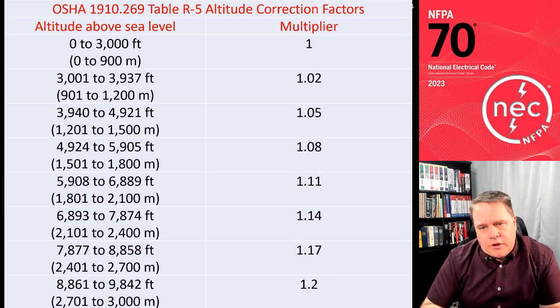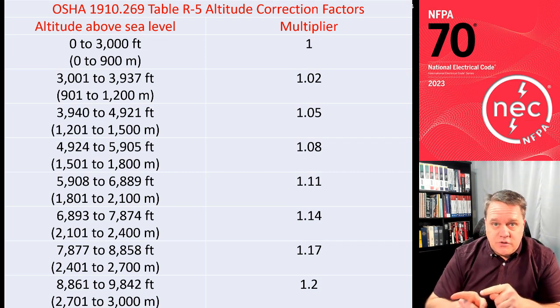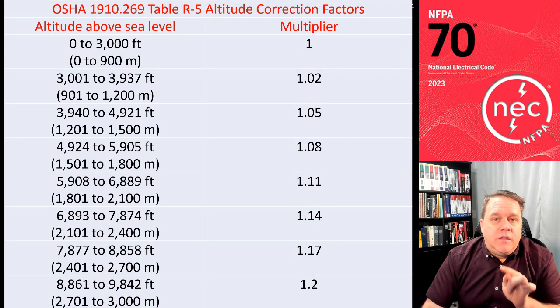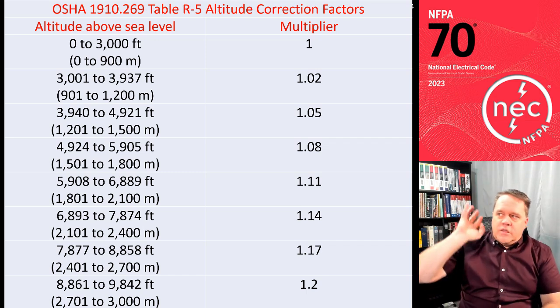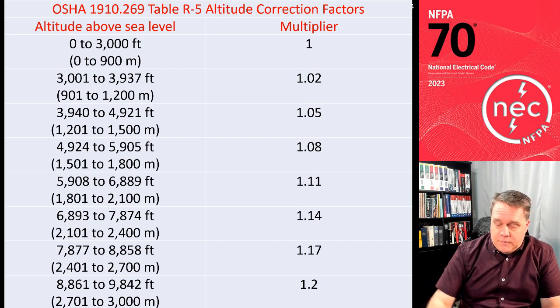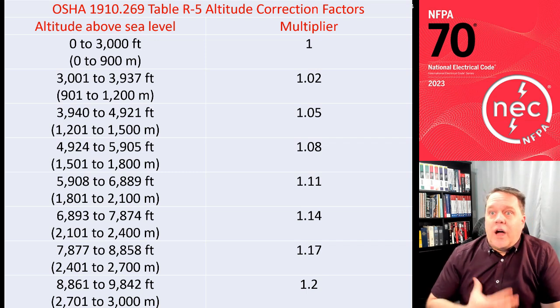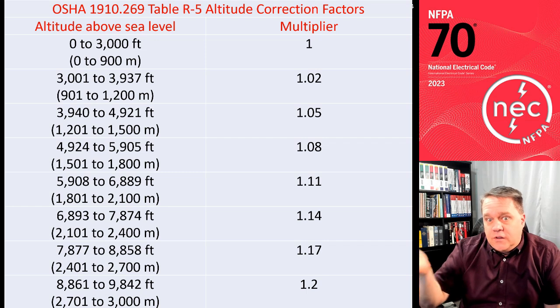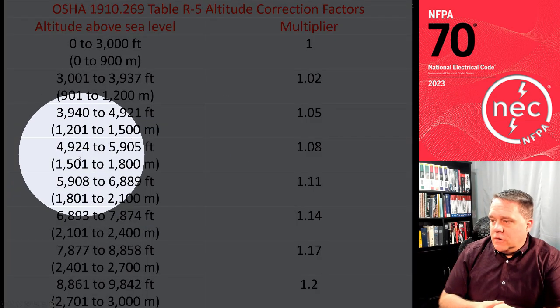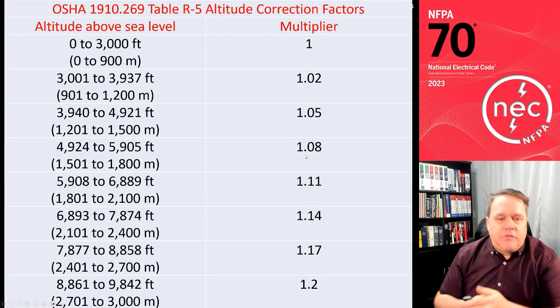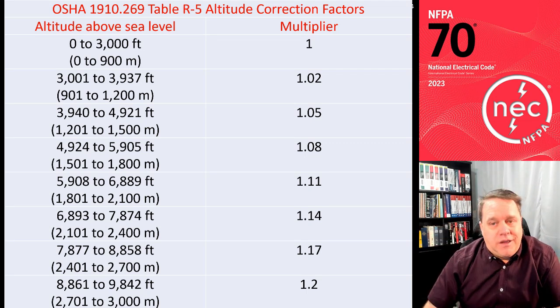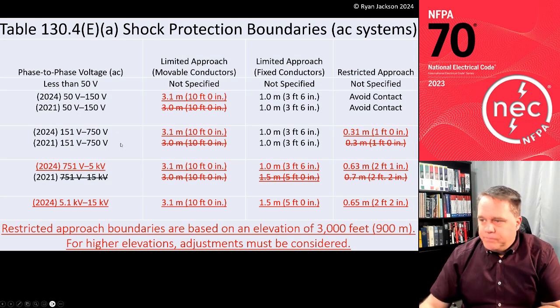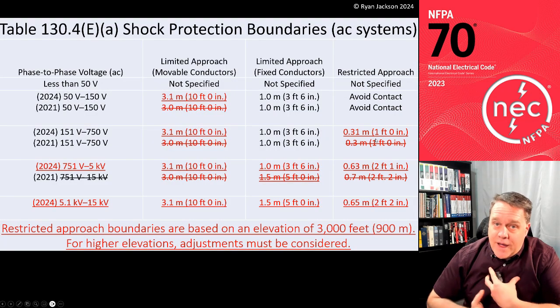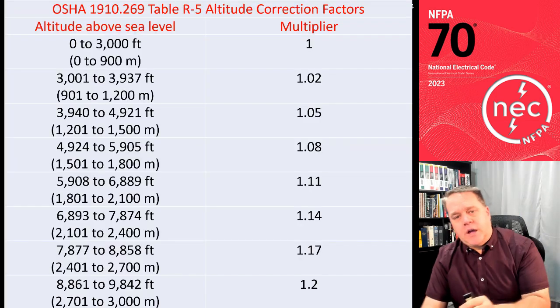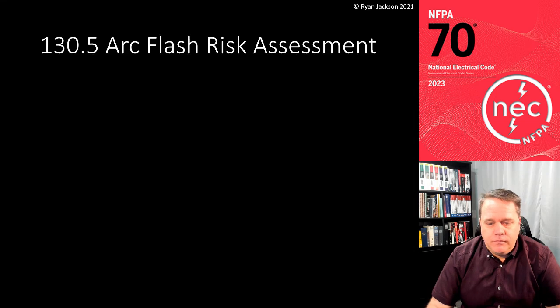So OSHA has this table here, and it says, look, you're going to take the approaches that we just talked about, the restricted approach, and you're going to multiply it by these correction factors based on your altitude. Okay, so this table here is actually not in NFPA 70E because the standard just says, hey, you might need to consider something. Well, I went back and I looked at OSHA, and I'm here to tell you this is what OSHA says. It says if you're at my house, 4924 up to 5,900 feet, I need to multiply those approach boundaries by 1.08. So you're going to get a slightly bigger value as you go up in elevation. So if the restricted approach is 1 foot, if you're at my house, it might be 1 foot, 1 inch. All right, so there you go. Need to consider the altitude when you're looking at restricted approach.